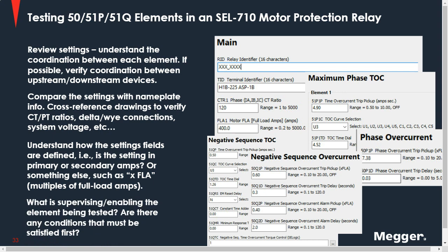And also, and this gets me very, very often, because we get into a groove, and we're assuming that the torque control or whatever is supervising that element is always going to be one, and that's not the case. It very often is not the case. And so when you're testing and you're not getting the pickup, you're looking at your sequential events recorder, where you have your SER set up specifically for certain elements.